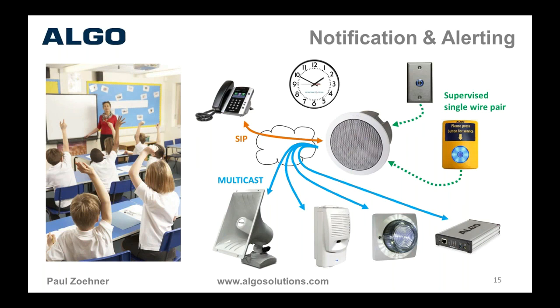Notification and alerting. There's so many possibilities here, it's really hard to capture them all graphically, but what you see here is a mix of endpoints. We have some of the speakers, we have the IP paging adapter at the bottom right, we've got some buttons on the top right. These are buttons that Algo offers, but you can also have any type of dry contact closure, normally open, normally closed in. Again, it could be a door contact, it could be a switch installed under a desk, it could be a smoke detector, it could be anything you imagine. Any one of these devices can initiate the alert.